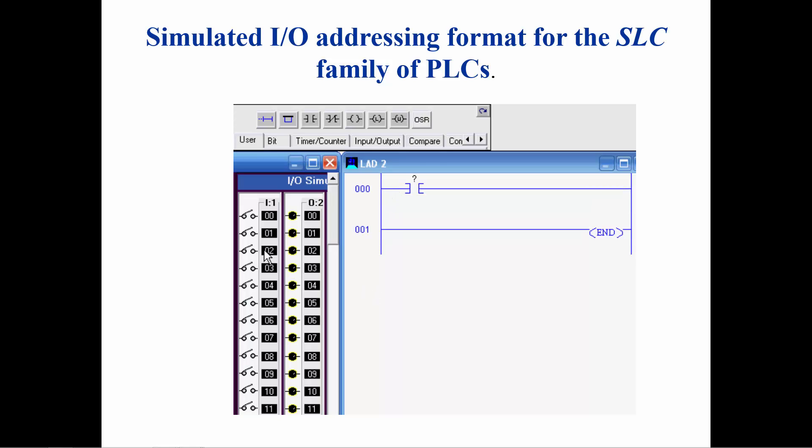With the simulation program you can then grab the address of the input that the instruction is supposed to reference, I colon one slash two, by clicking on the input and dragging the address to the instruction. The address will refer to connection two on the input module in slot one.